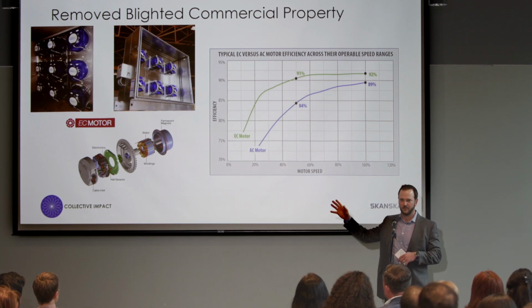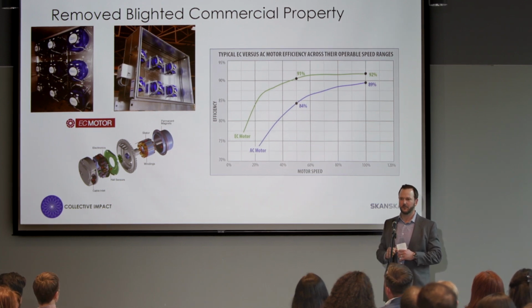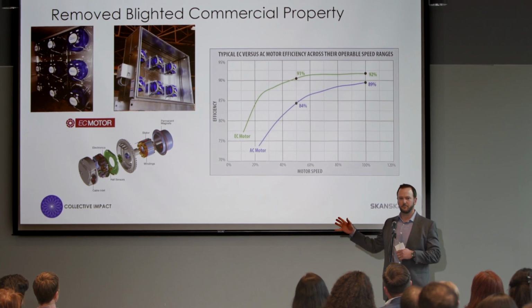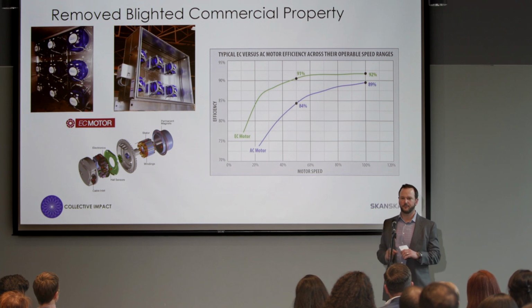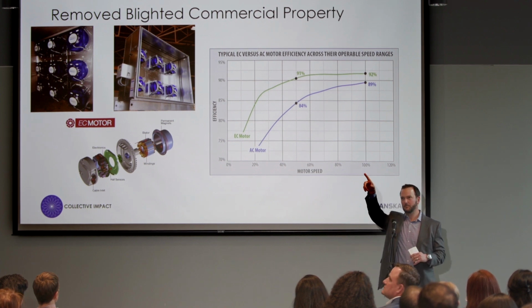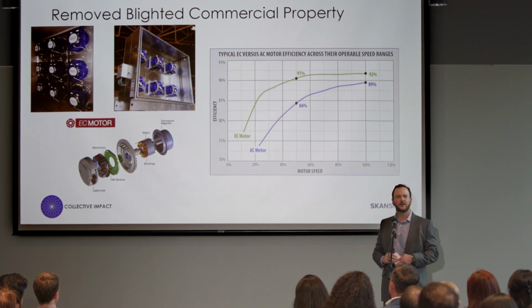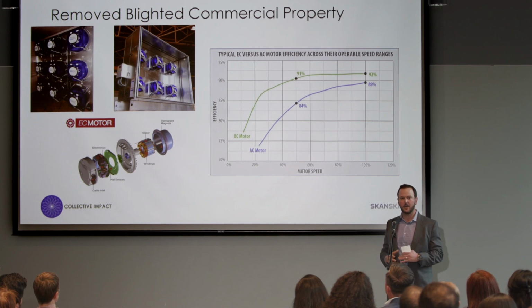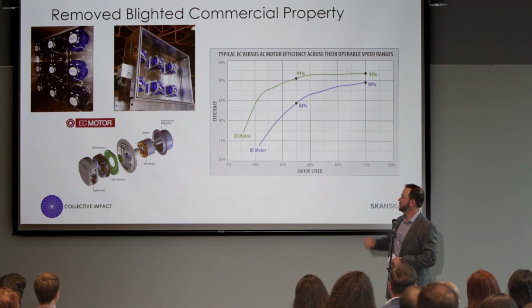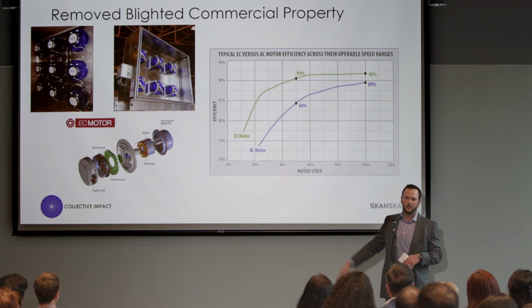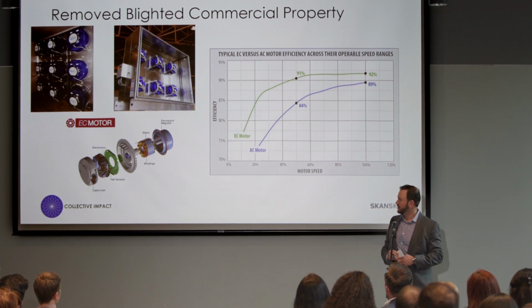They don't take a variable speed drive to ramp up and down. Variable speed drives have all these inherent electrical losses. These motors have been around for maybe two decades, but in fractional horsepower applications, like in the fan-powered boxes above the ceiling. In the past maybe five years, they've scaled up to full air handling unit systems with big motors — fan arrays are an example of a big built-up system.